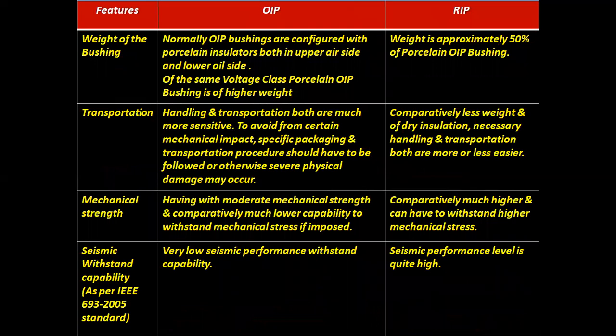Weight of the bushing. Normally, OIP bushings are configured with porcelain insulators both on the upper air side and the lower oil side. Of the same voltage class, a porcelain OIP bushing is higher in weight, whereas for RIP bushing, the weight is approximately 50% of porcelain OIP bushings.